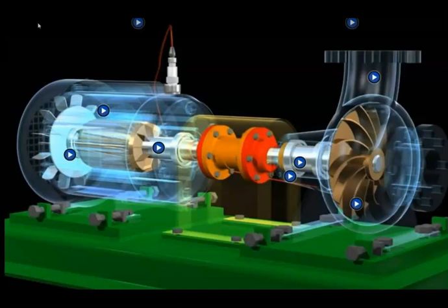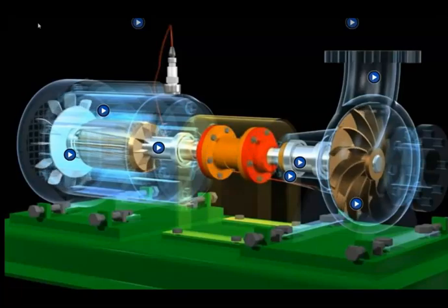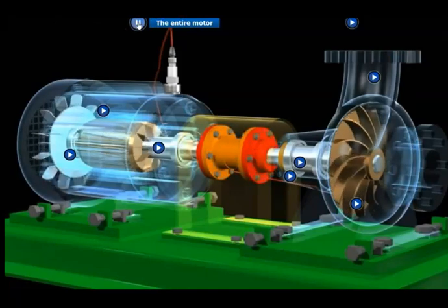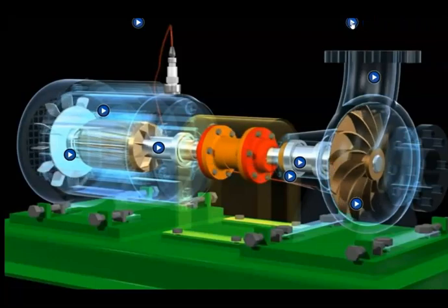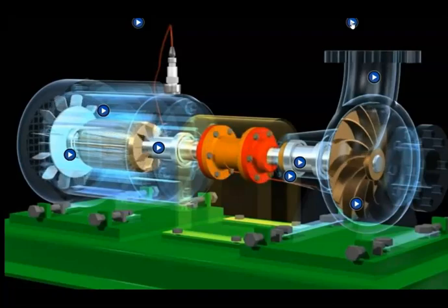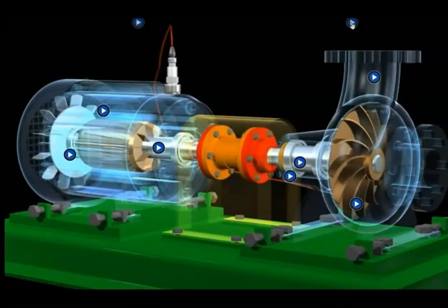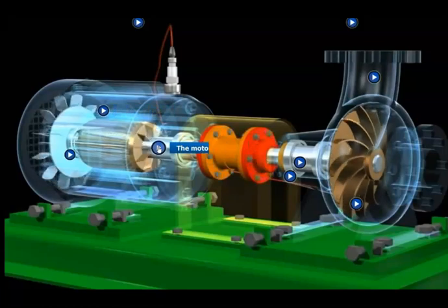Now we hear vibration sound generated by the machine. Vibration lets us see inside the machine, so to speak. If you just listen to a machine, it might make a sound — and hopefully you can hear that — and the pump may make a certain sound. That's not a very healthy sounding pump. What vibration analysis allows us to do is break that sound up into all its individual components, because those individual frequencies actually relate to different components within the machine. As those frequency components change, it provides an indication of whether there's a problem with the bearings, or the rotor bars or the shaft, which can be misalignment, unbalance or anything like that.